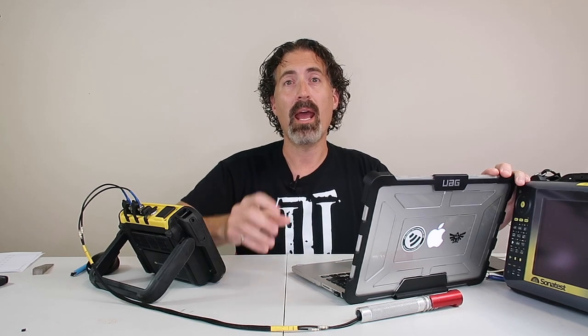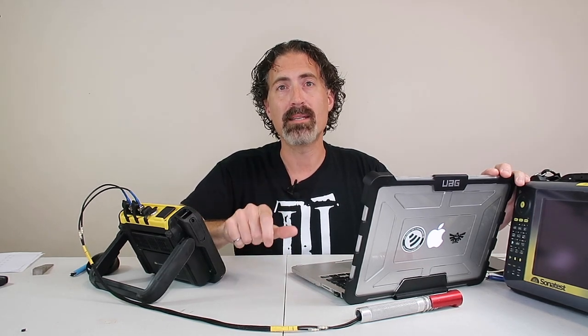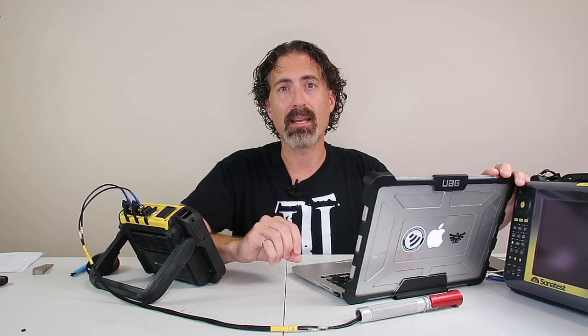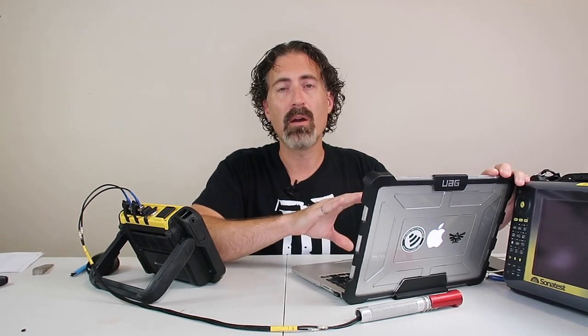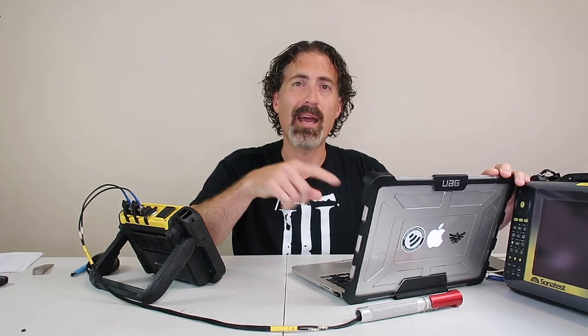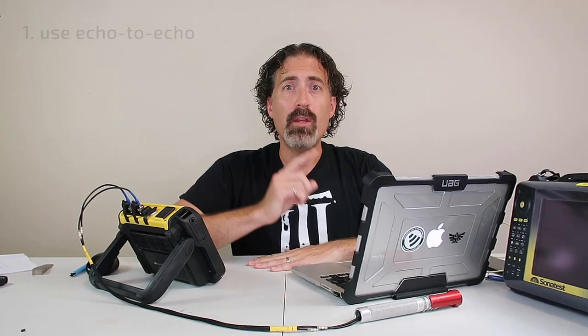It's far too much. And the reason for that is that the probe tip heats up and it messes with the length of that delay line. And when you use first echo, it will include that. When you use echo to echo, it takes that out. Lessons learned. Number 1, use echo to echo when you're doing high temperature thickness readings.